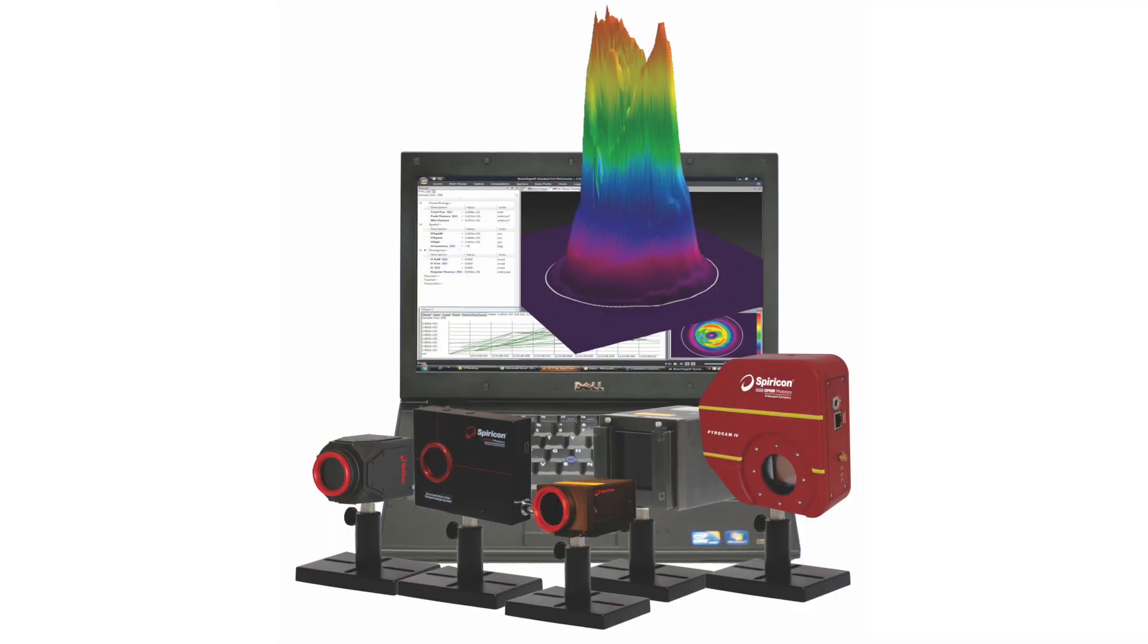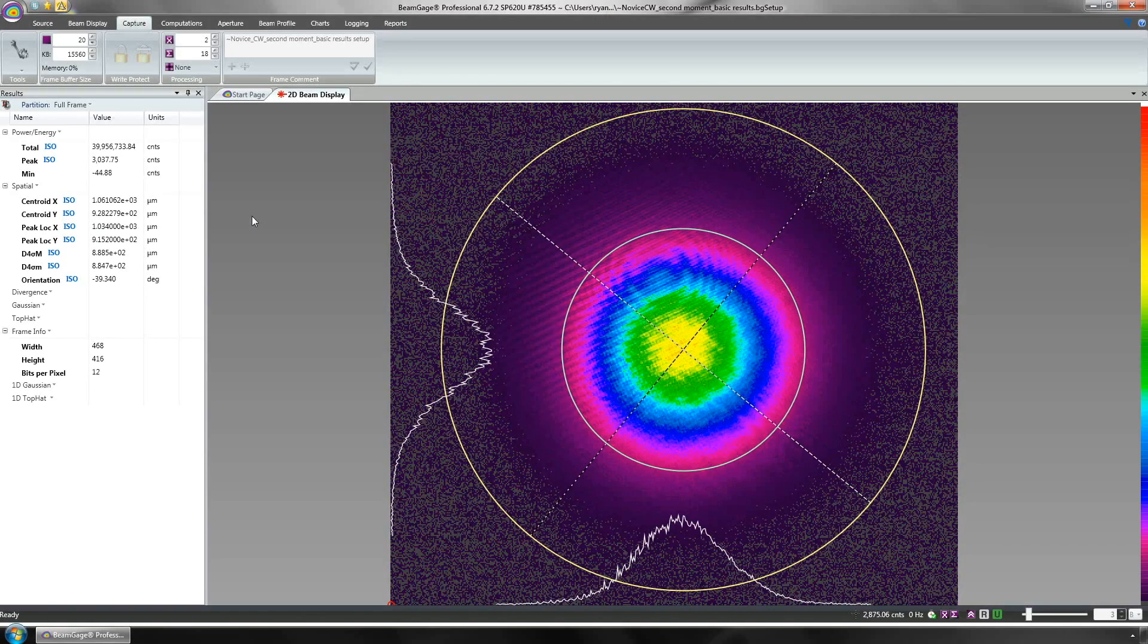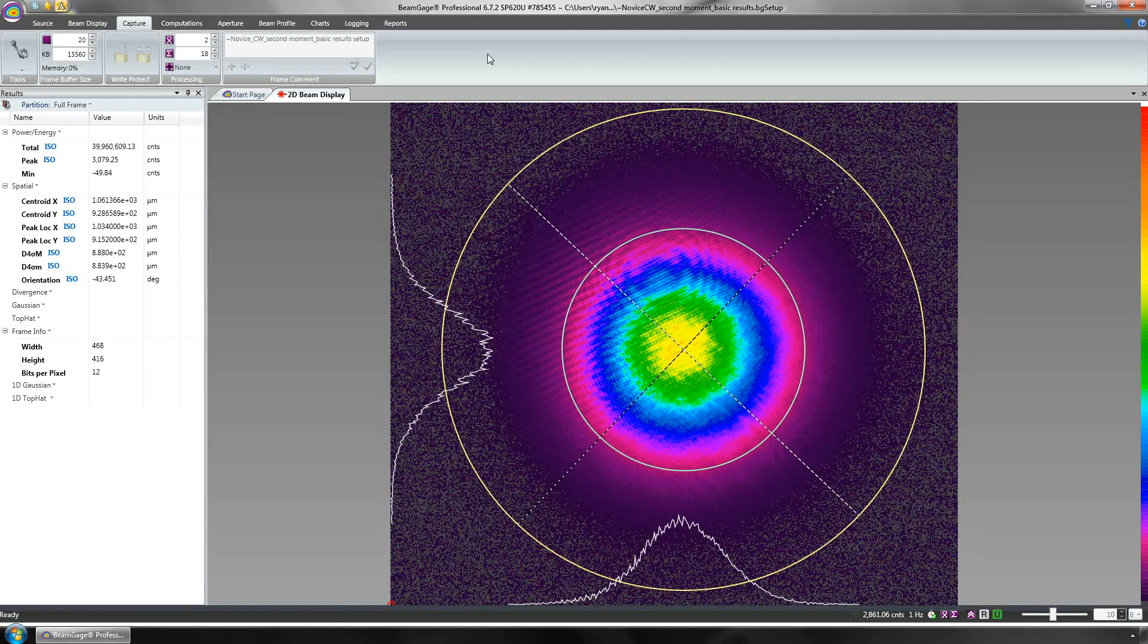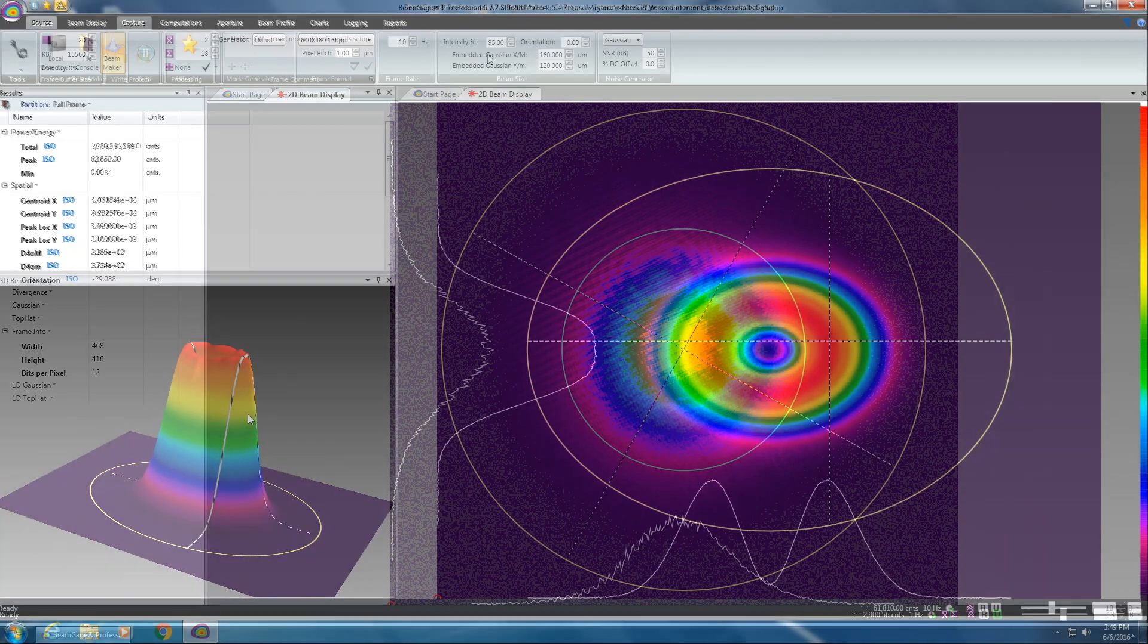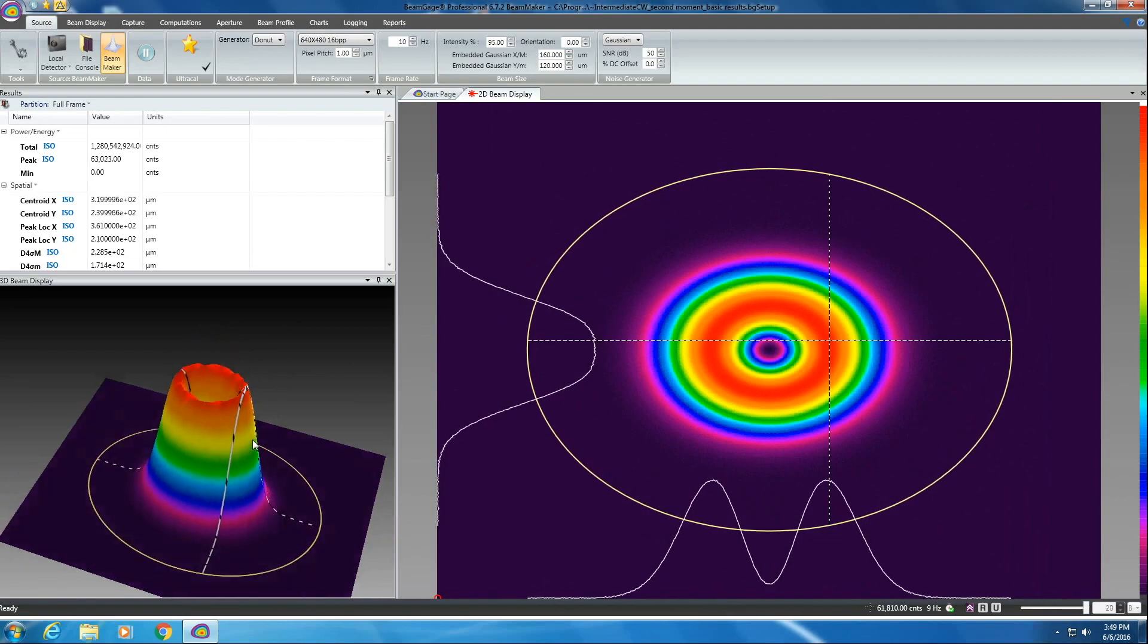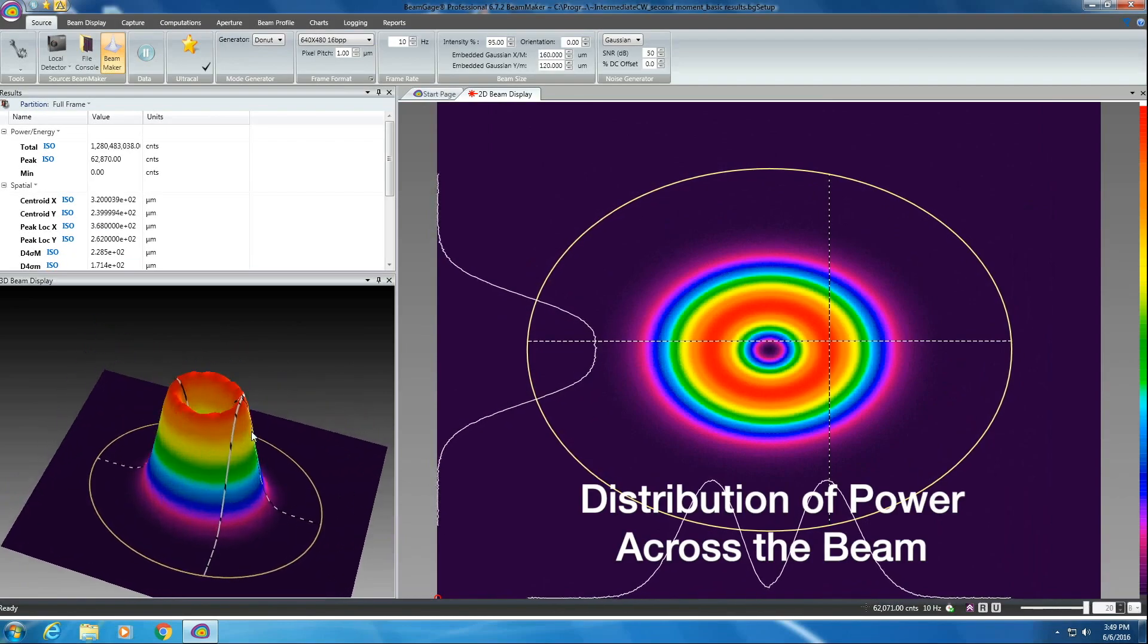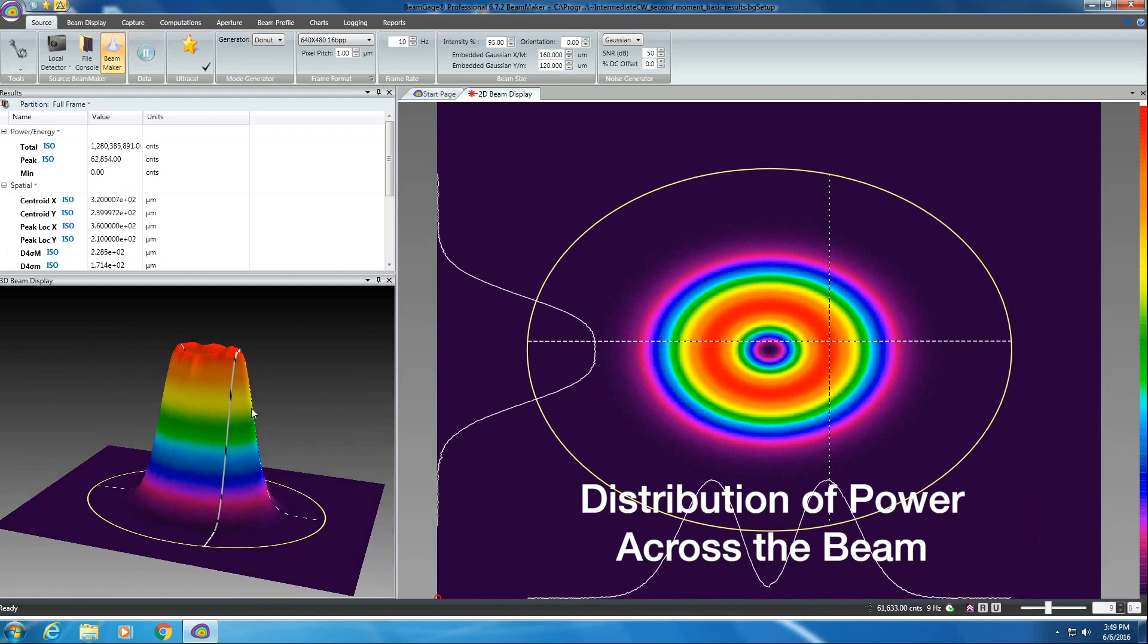A camera-based profiler is best when measuring a pulsed laser with a relatively low repetition rate, or the most important measurement is the distribution of power throughout the beam.